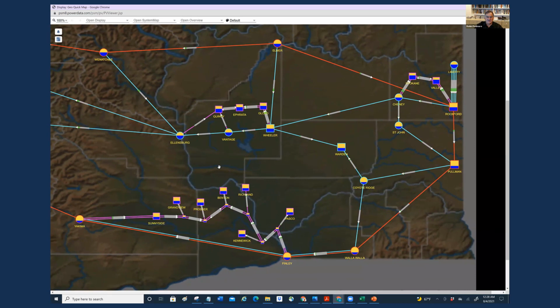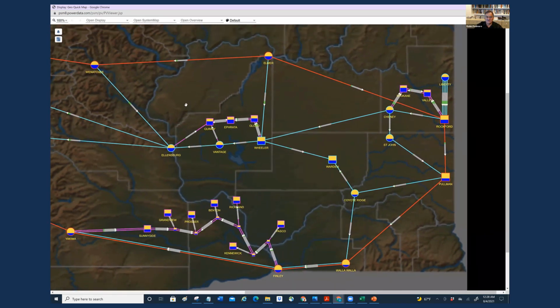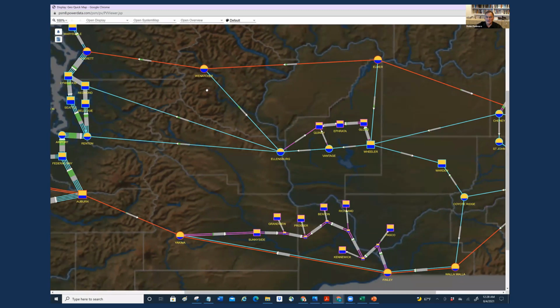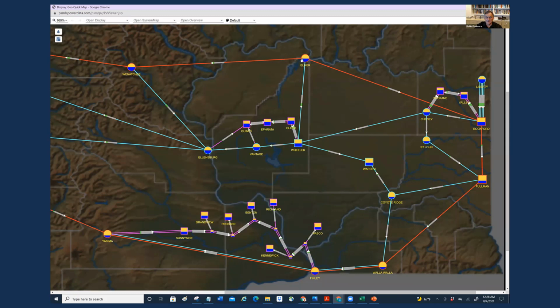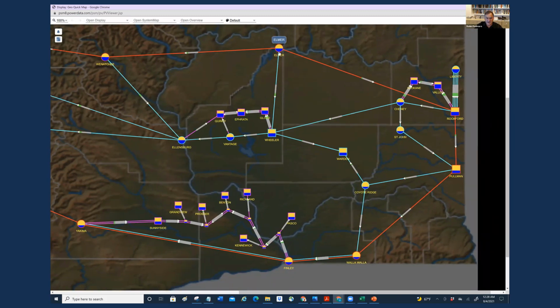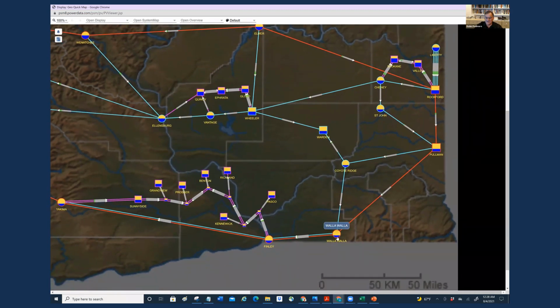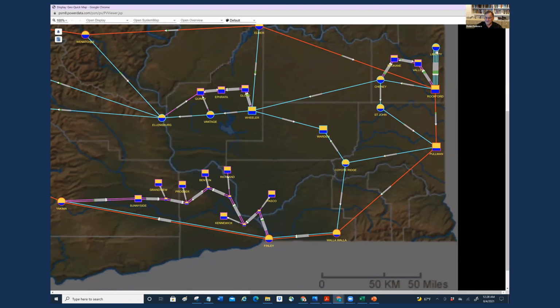So to apply the electrical distance diagram to this situation, we've got to know which generators will supply supporting megavars. Now, in the case of Elma, it has support coming from Liberty over here, and it will have support from Wenatchee. Those are pretty much the closest large generating units, electrically close to Elma. And really, in this case, we believe we can get a pretty good approximation by looking at, if I add a reactor here, I will get support from the Elma units, the Wenatchee units, and the Liberty units. On the other hand, if we add a reactor at Walla Walla, we'll get support from Liberty.